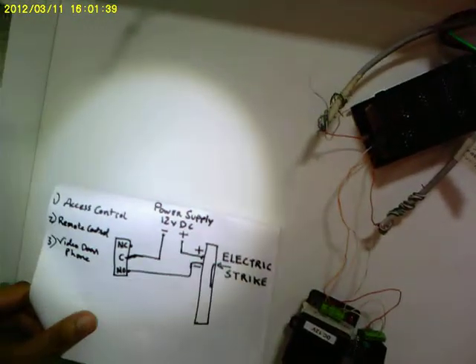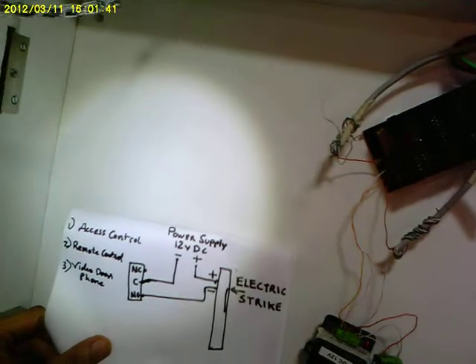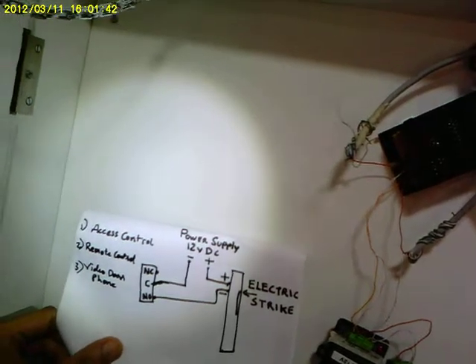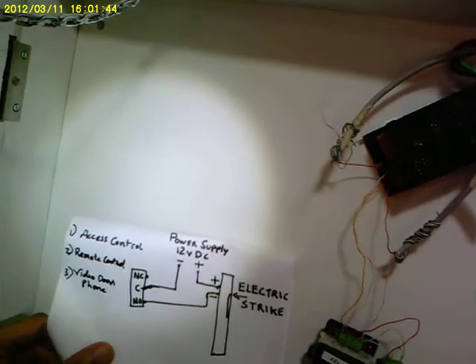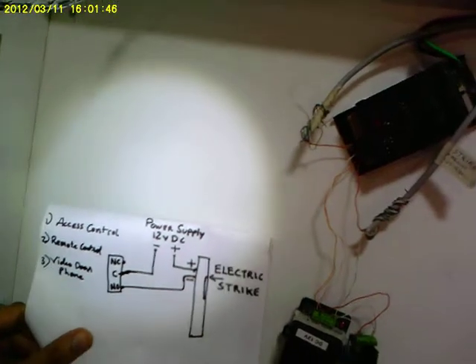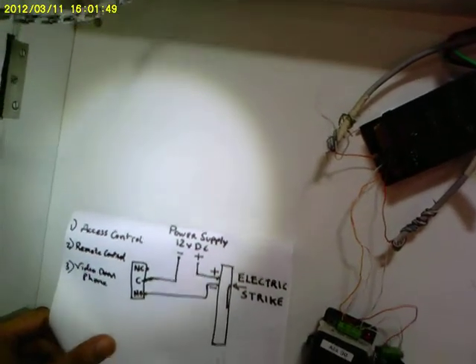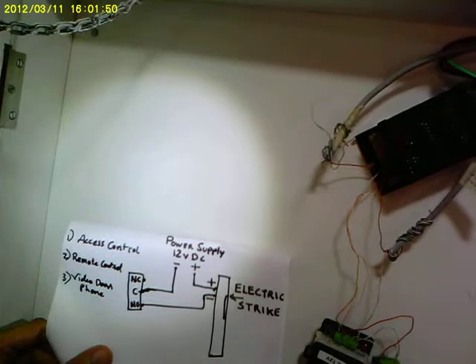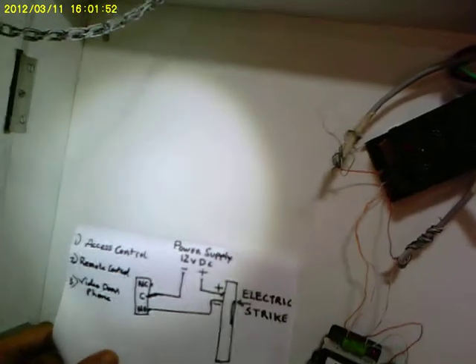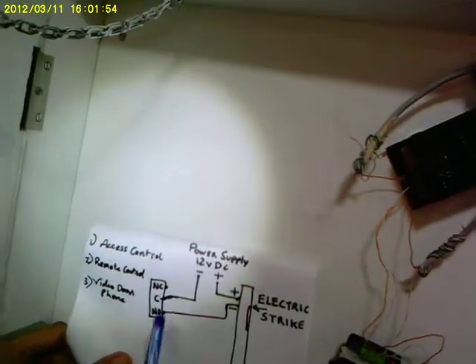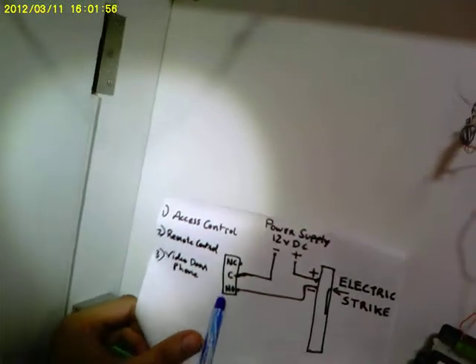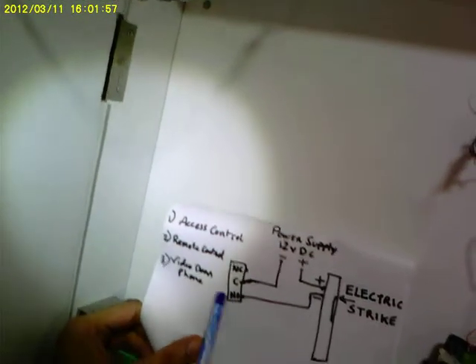Now, what you need to understand is, since electric strike only uses current or power when it needs to be operated or when it needs to open the door, it's always connected to the NO or normally open of the controlling relay.